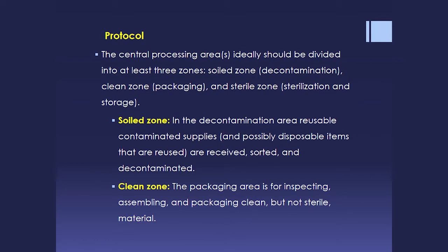So according to protocol, your clinic should have a separate area for sterilization. Again, we have a limitation of space in our dental clinics, that's why this is not possible in many clinics. Those clinics which are NABH accredited or maintaining protocol according to NABH standards must have a separate zone or room for sterilization, or a separate processing area for sterilization. Again, you have to divide this area into 3 zones. The first one is the soil zone, where you will receive all the contaminated instruments and perform the cleaning procedure. Then the second zone is the clean zone.